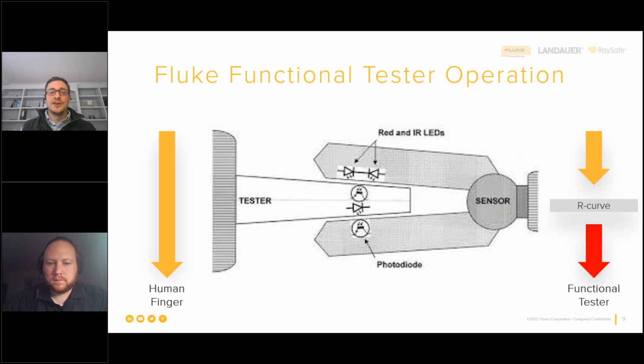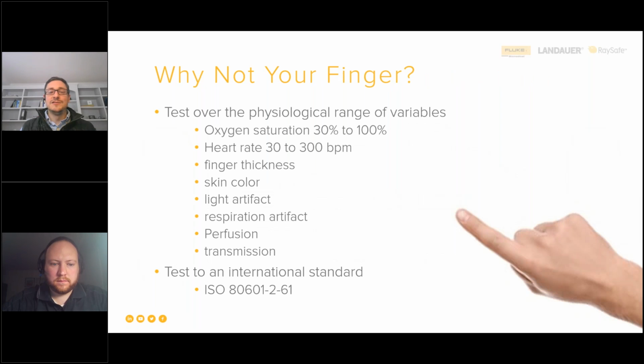On the next slide, we're going to talk about why not use your finger, right? Your finger can test only for the state of your finger, right? Which you don't know. You don't know what skin tone you have, right? You don't know what thickness your finger falls into. But a typical healthy patient has a very stable SpO2 in the mid to high 90s. What if you're at 98 one day and 94 another? How can you ensure the consistency of that test? So what a functional tester does is it allows you to vary the settings across a wide range of physiological settings that you can't do with a finger. So, that's one thing to consider.